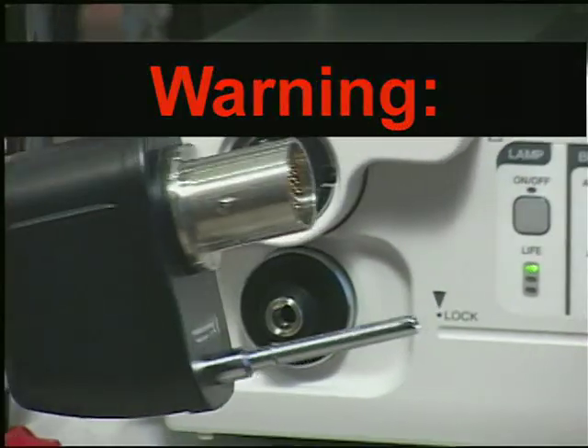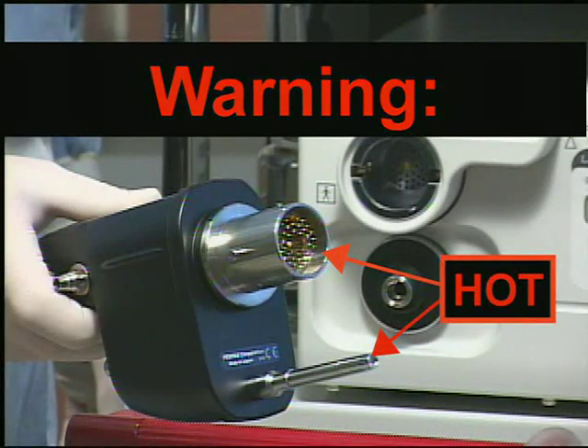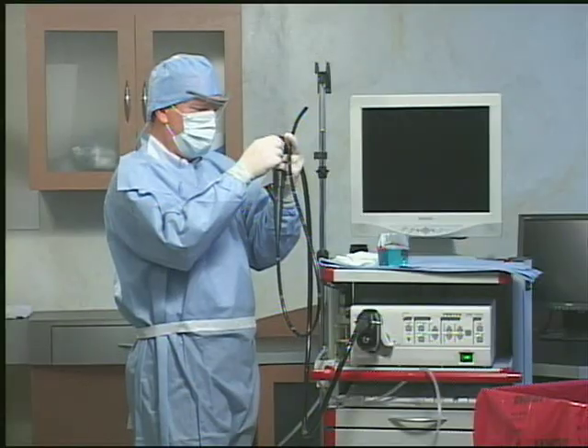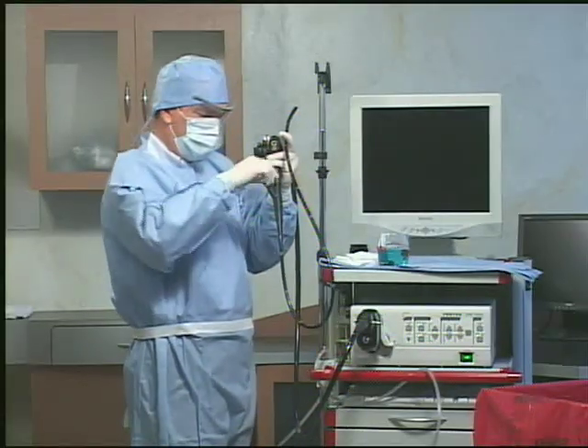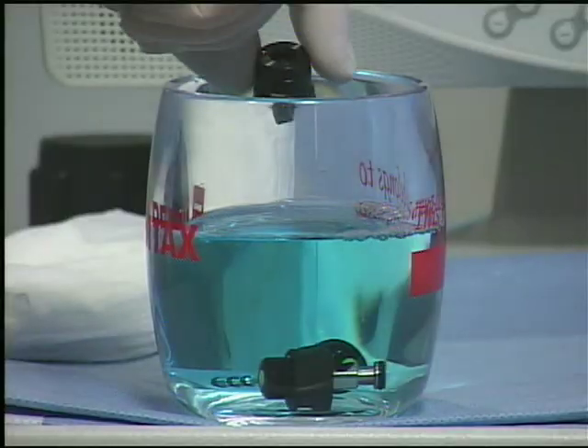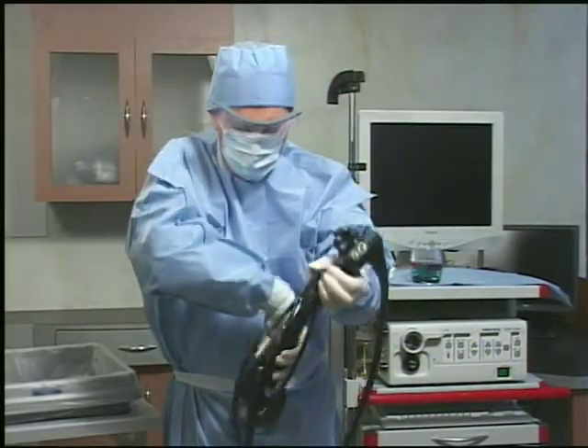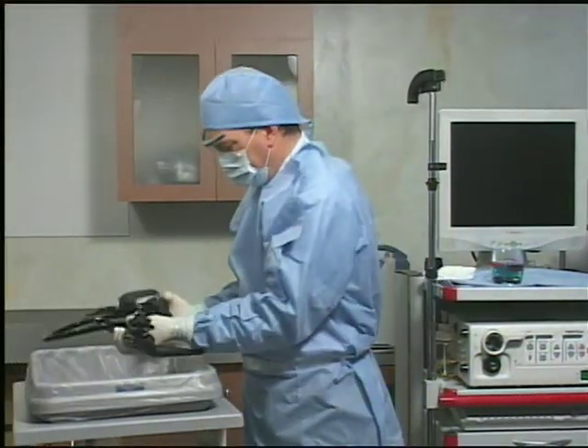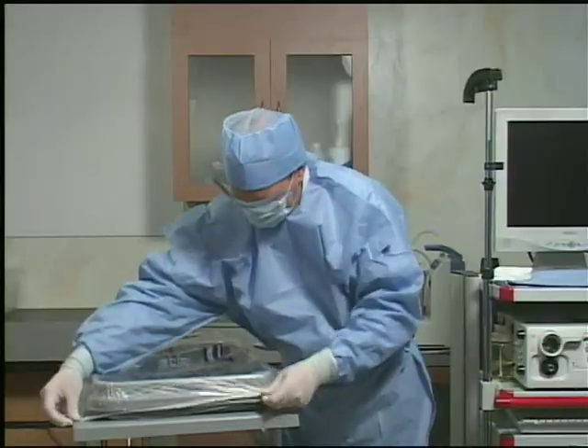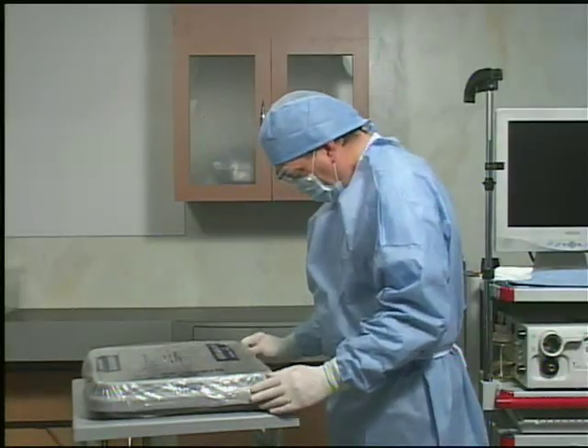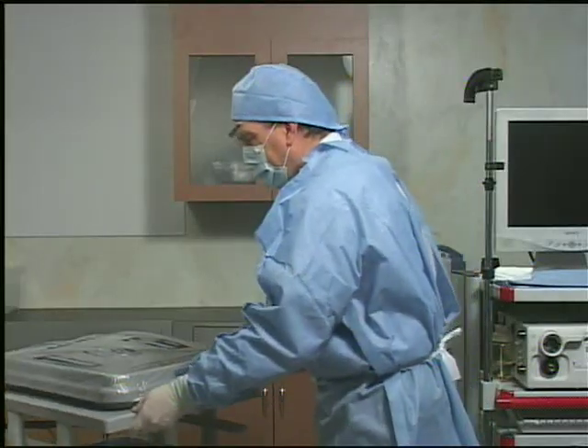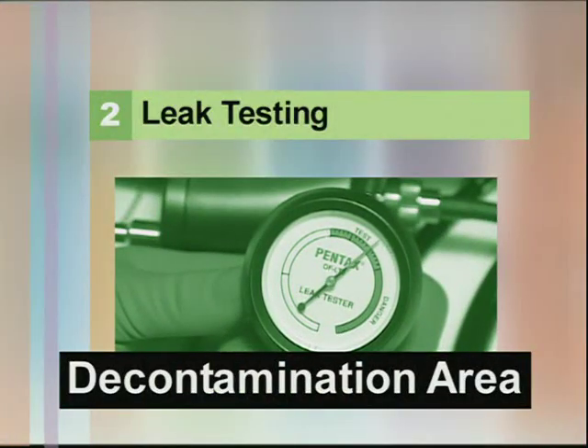Warning: immediately after use, the light guide prong and the electrical contacts or pins of the endoscope may be hot. To avoid burns, do not touch these areas immediately after use. For safer handling, grasp the PVE connector housing. Remove all endoscope components, suction valve, air-water valve, etc., and place in a container of enzymatic detergent solution. Carefully coil the insertion tube and umbilical cable. Place the scope in a covered transport container, minimizing exposure to potentially contaminated patient material, and carry the scope to the cleaning room. Leak test in the decontamination area.